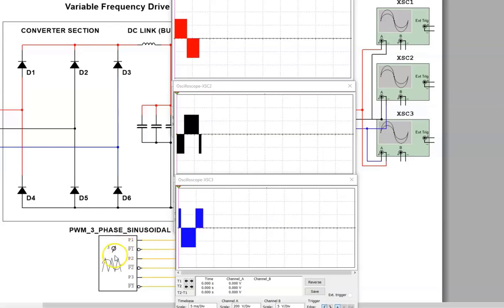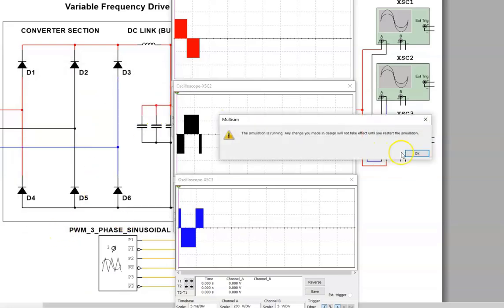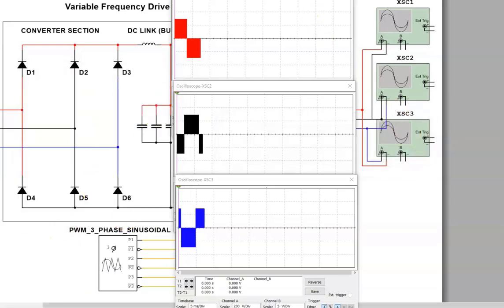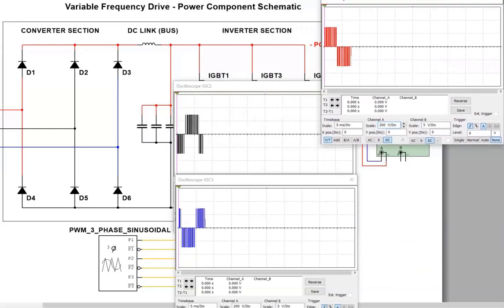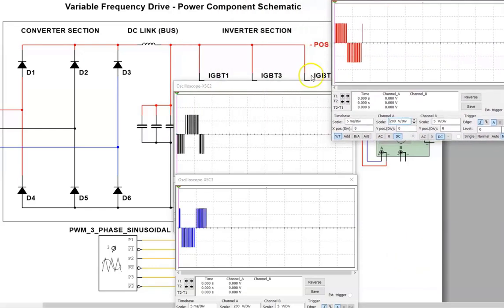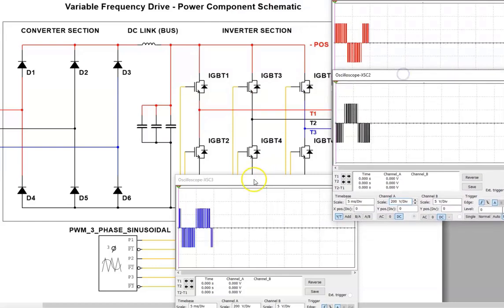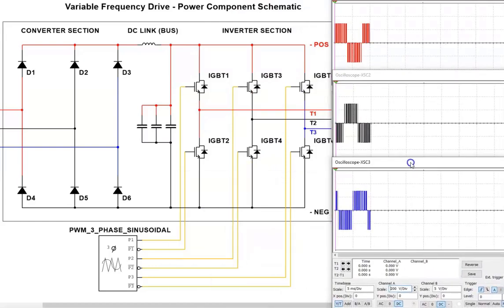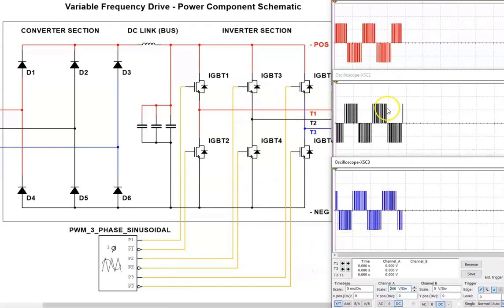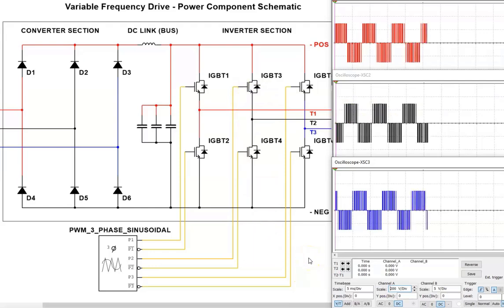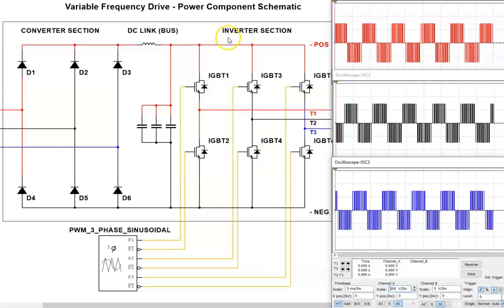So I'll just set it back down to 2 kHz. And then we'll wind this up. So that's what you see on the output of the drive. When you're measuring these things, you have to take that into account. If you've got one of your transistors blown out, you're going to see a problem when you're troubleshooting. They talk about testing the IGBTs or having a short circuit fault at the IGBTs. They're talking about the output transistors that connect directly to the motor leads. And they are in the inverter section.